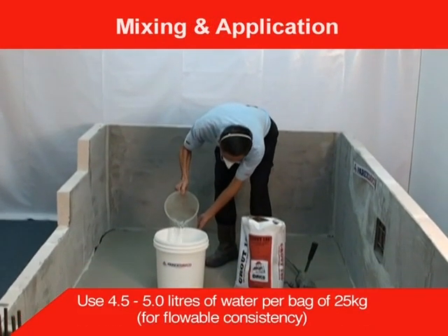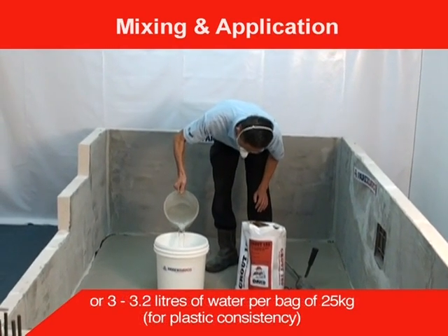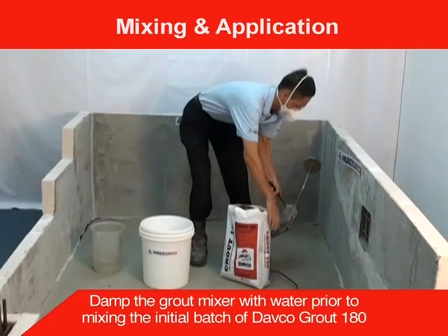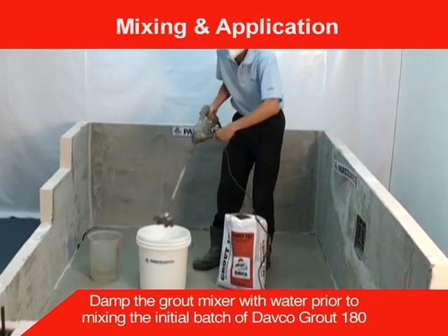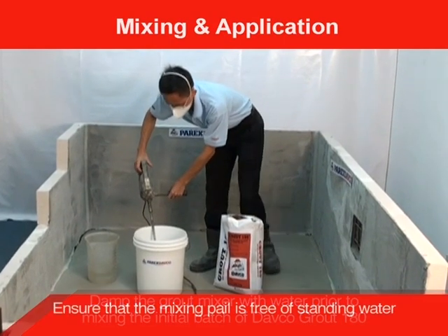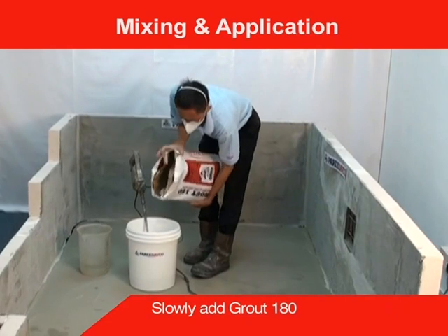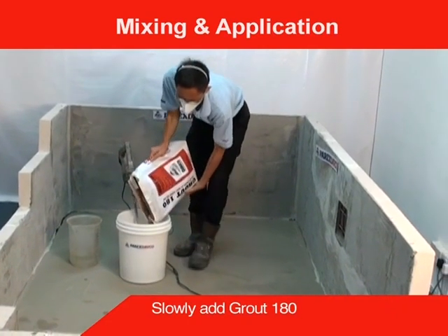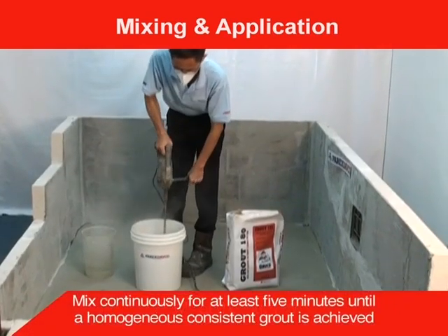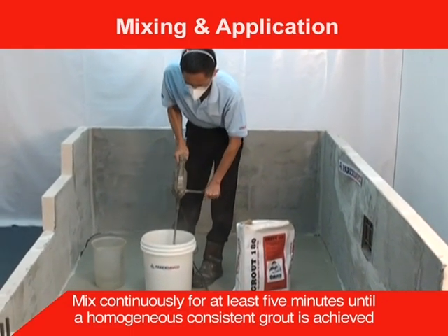Add 80% of the pre-measured quantity of water. Damp the grout mixer with water prior to mixing the initial batch of Davco Grout 180. Ensure that the mixer is free of standing water. Slowly add the Grout 180, mixing continuously for at least 5 minutes until a homogenous consistent grout is achieved.